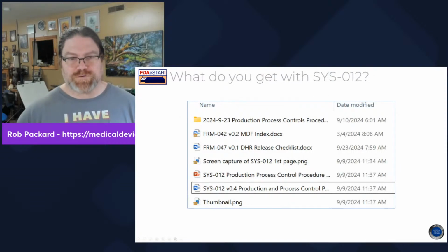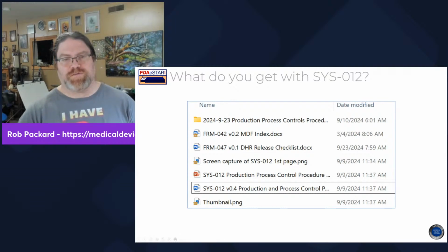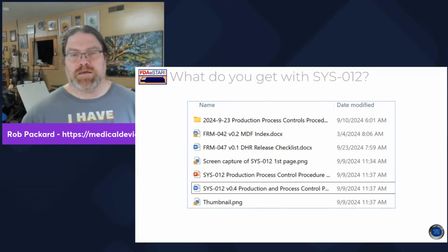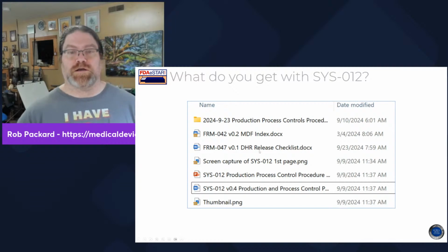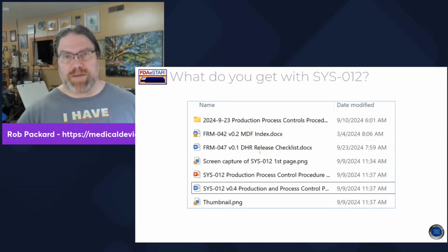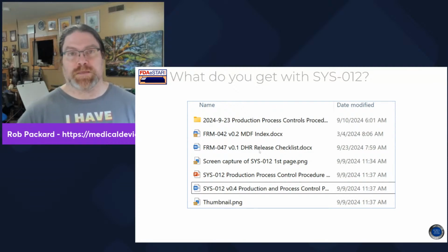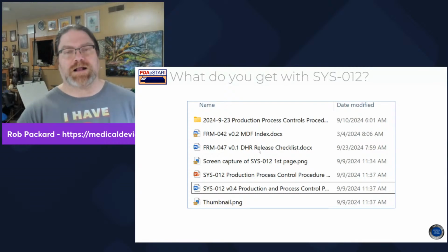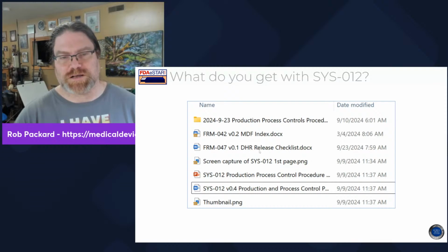There's a copy of the procedure, the native slide deck, a screen capture that was used for the thumbnail on this video, and a checklist for a device history record or batch record release checklist. This is usually used to make sure all the contents of your batch record are included before you release product. You don't want to have any paperwork missing. One of the things that often is missing is, if there were any nonconformities, a copy of the nonconformity would be included in that checklist.